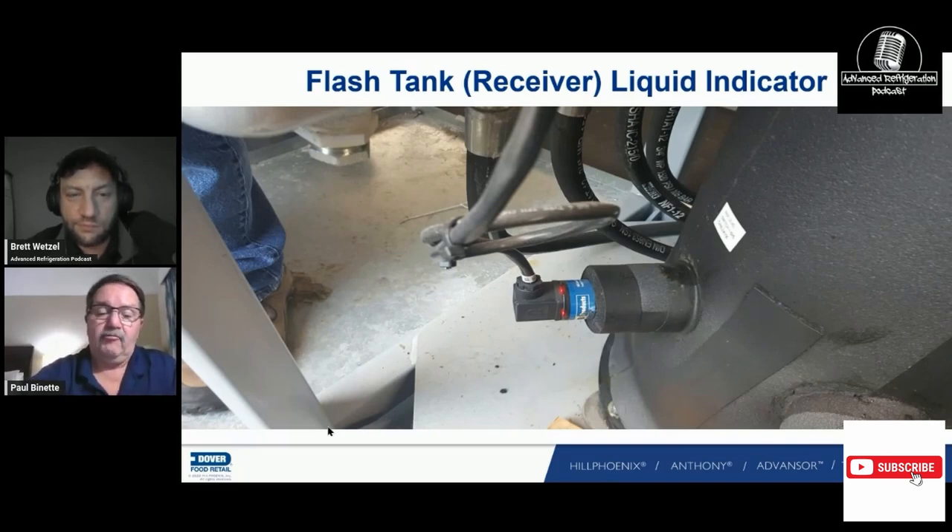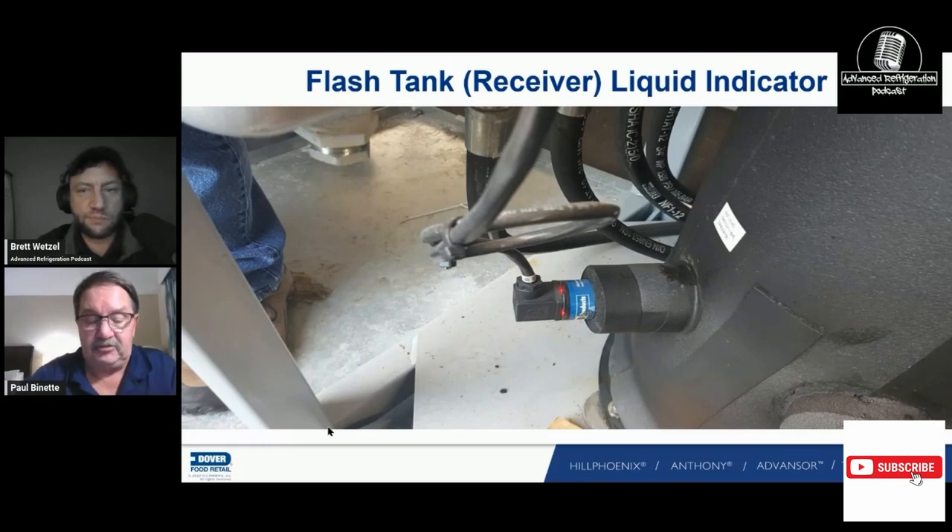This switch head is not compatible with and cannot be transferred over to the oil sensor if you lose it. We charge our vessels through the bottom charge station on the vessel itself — that's how our factory and training program teaches it. If you lose gas, you can charge through there while the rack is still running, taking the bottle down to the vessel pressure. If your charging line gauge hits 550, you're not going to transfer any more liquid.